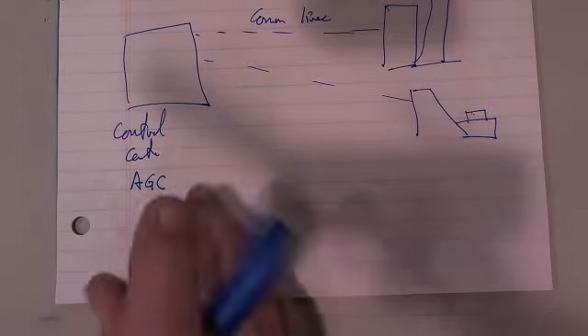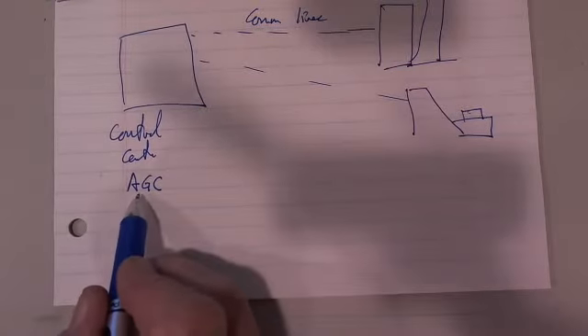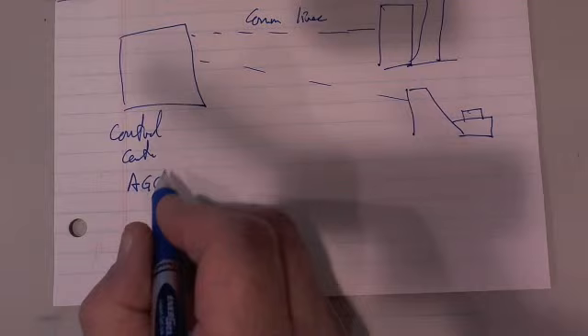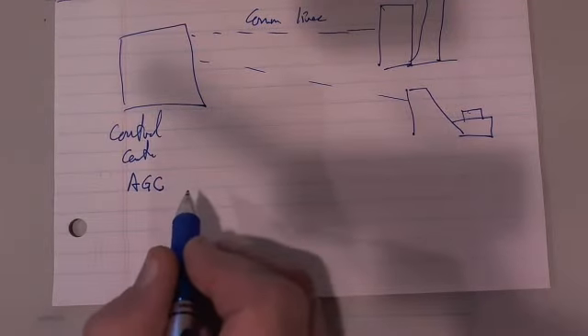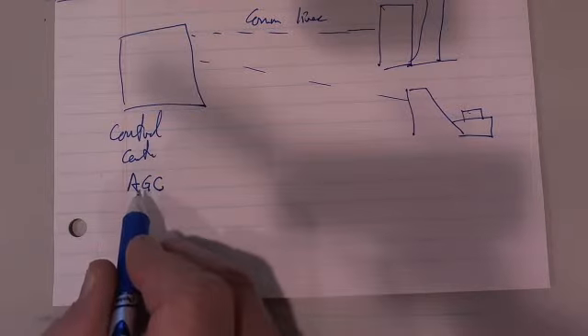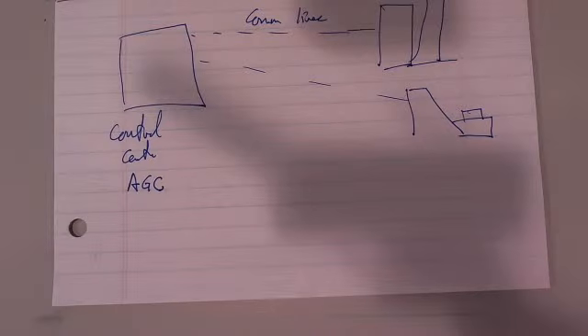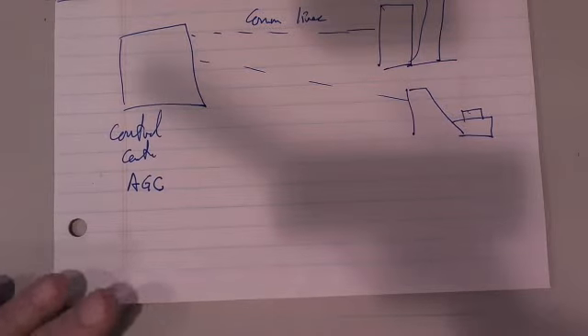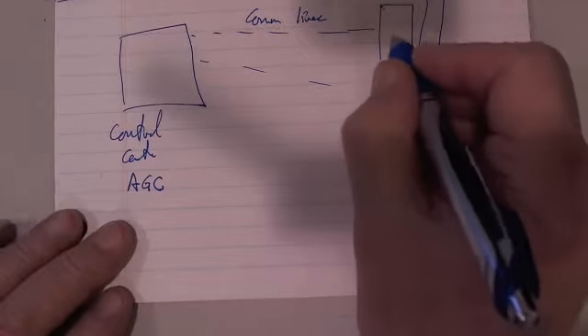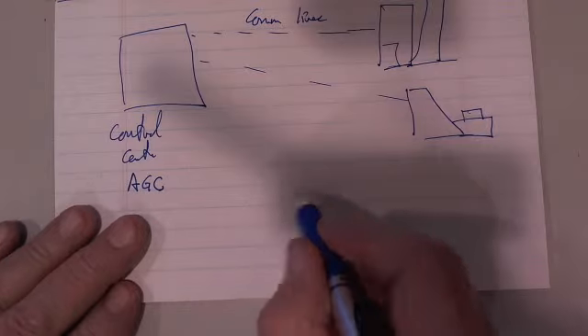The original AGC programs or LFC programs were actually performed on an analog computer. I have a feeling here that when I say analog computer, people look at me and think, what's that? You can build a computer with operational amplifiers that do integration, and you set up all the differential equations with feedback loops on it, and it'll solve the differential equations instantaneously, and you can have a control system set up on an analog computer. That is gone away now. Almost completely. It's always done by sampling and getting digital input and running a digital computer program where you have much more flexibility. And then down at the plants, inside the plant, we have, let's take a steam plant.